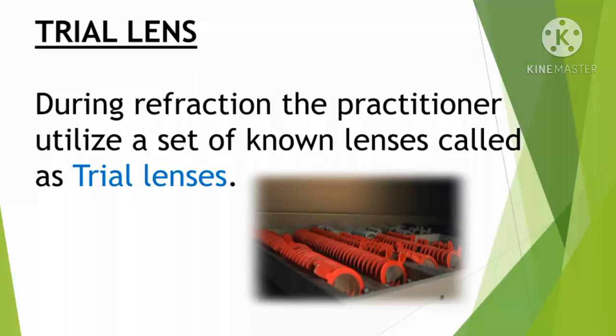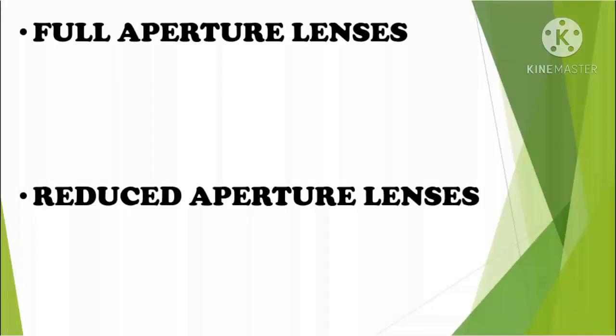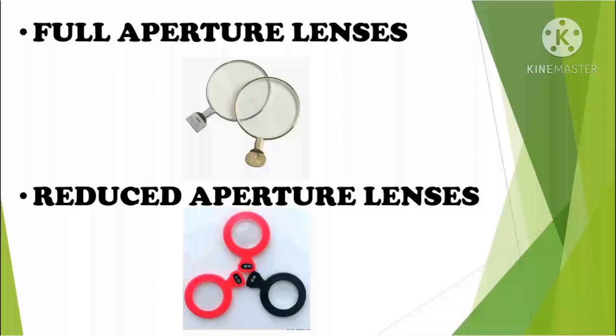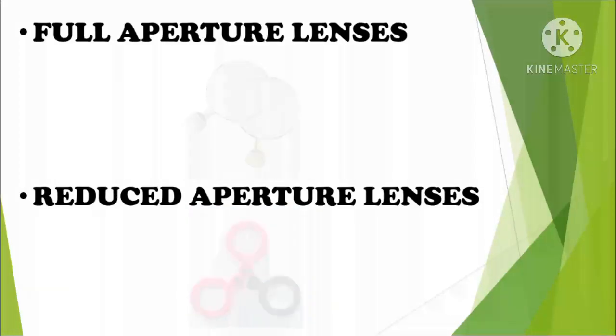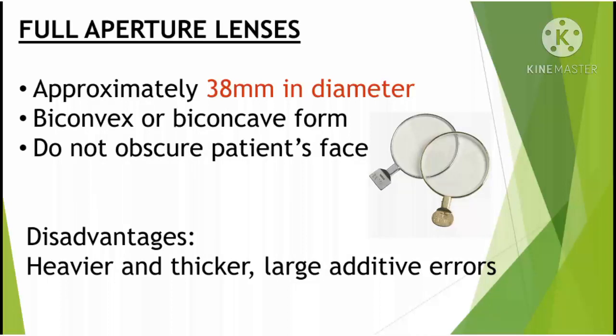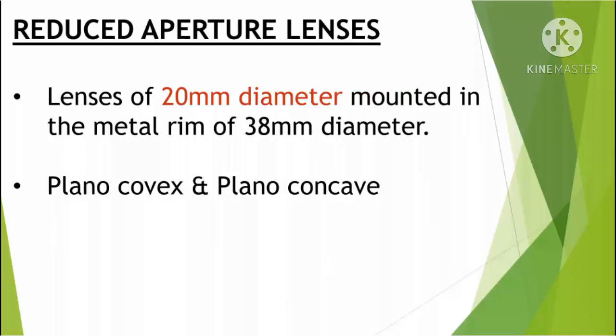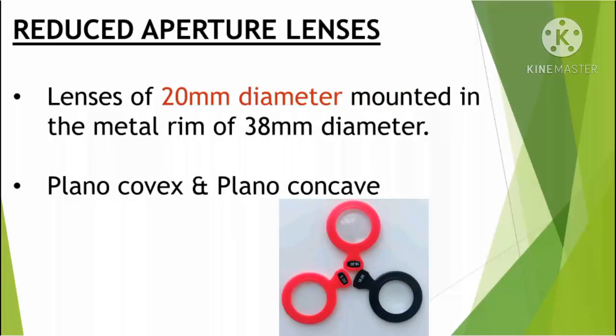Trial lenses are used during refraction time to correct refractive errors. Trial lenses come in two forms: Full Aperture Lens and Reduced Aperture Lens. Full Aperture Lenses have a diameter of 38 mm; they are bi-convex and bi-concave spherical lenses, but they are slightly heavier compared to Reduced Aperture Lenses. Reduced Aperture Lenses have a metal rim on the corners and a lens portion of 20 mm diameter; plano-concave and plano-convex types are both available.